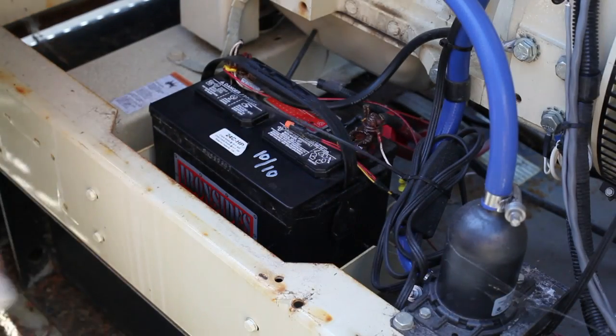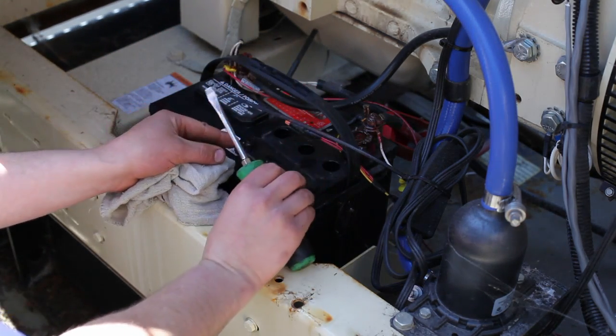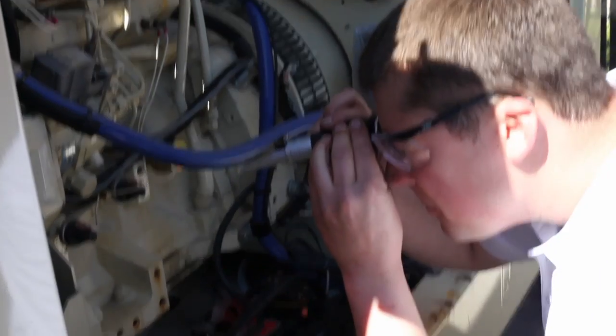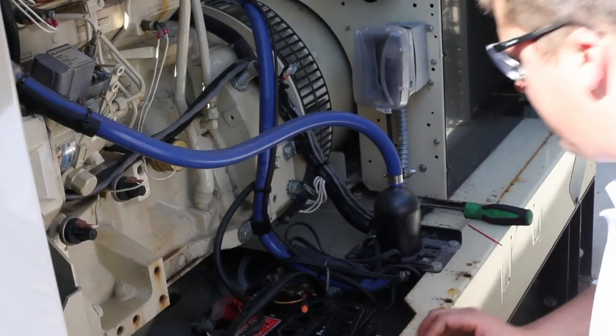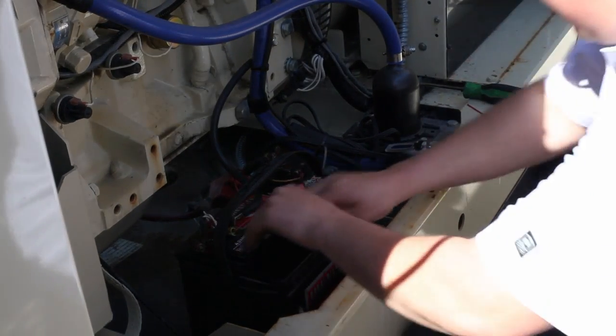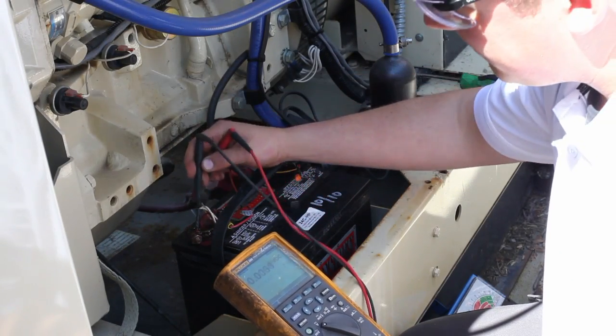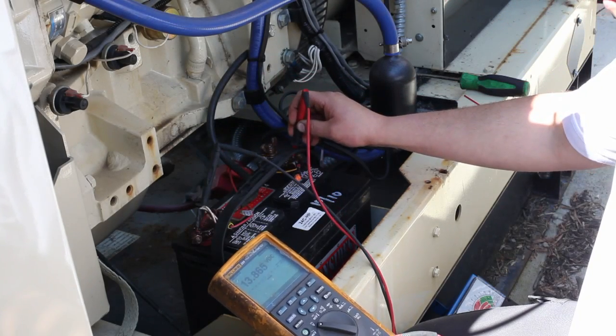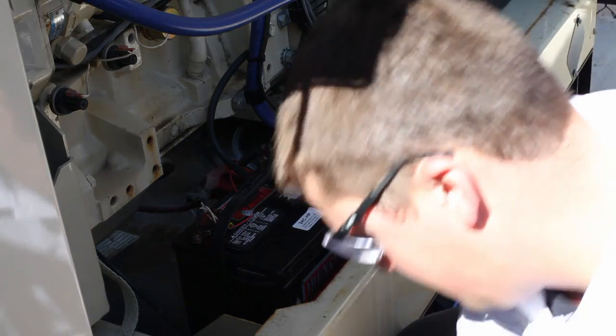A typical planned maintenance contract visit will carry out battery maintenance service and checks including: check all battery and starter connections, remove cell caps and check electrolyte levels, take electrolyte samples and examine with a visual test device, replace caps after checking, examine battery cleanliness, and connect an electronic tester to verify battery cell voltage stationary and during run-up. If the tester reads close to battery voltage at no load but drops significantly when load is applied, it is a strong indication the battery needs replacing. Obtain a printout of battery condition and ampere hour capacity.